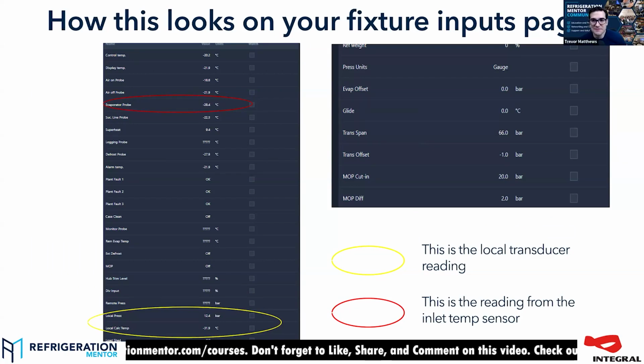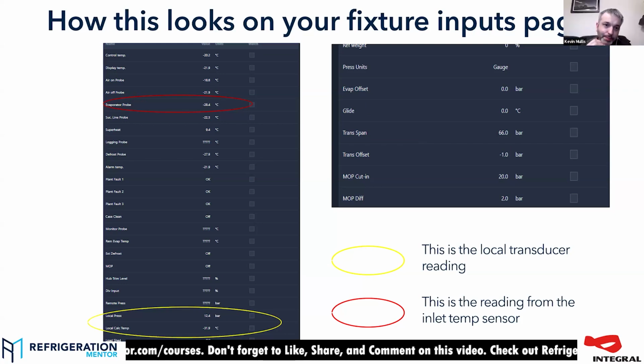Okay, so when you've connected up your transducer and your probes properly, you'll have a screen on your inputs that looks something a little bit like that. So assuming you've connected it directly to your controller, the bit circled in yellow there is where you will read the evaporating condition. It will tell you your local pressure and what it's worked the temperature out to be. That is the number that the controller will use to work out the superheat, which you can see just below the red circle, or higher up the image there.